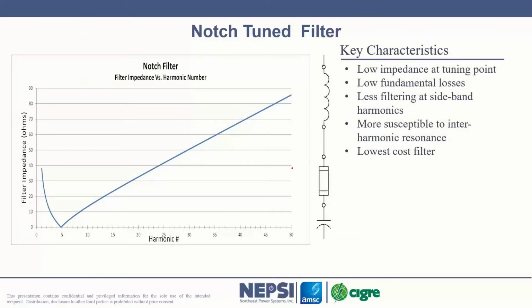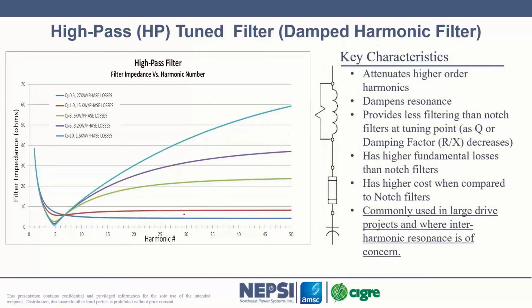Can't get into it too much. When you look at the characteristics of a notch filter, it's very simple. We come from the impedance at the fundamental, we drop down to a tuning point, in this case around 4.7, and then we shoot up. Very simple. We have a low impedance point where we have set the X of L at a ratio about, in this case, 1/4.7 squared of X of C. And we're going to get into the calculation in a minute.